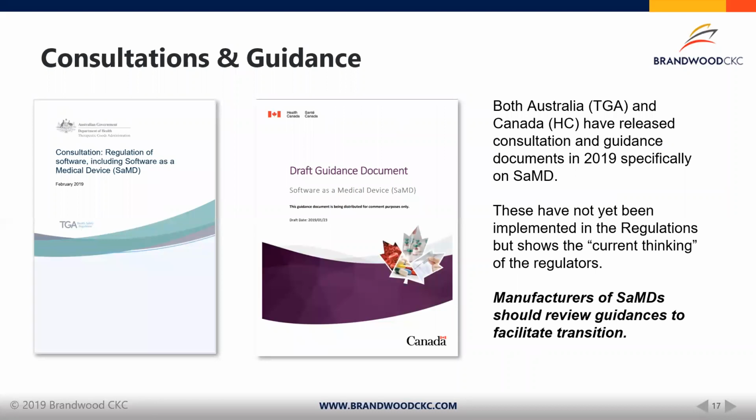In Australia and Canada, there have been some consultations recently. The consultation in Australia, I think, was closed in March this year. Nevertheless, even though those changes have not been formally implemented yet in the regulatory framework, guidance documents provide the view of the regulator as it stands. So both Australia and Canada have released those consultations. They're available online. They're specifically focused on software as medical devices. And as I mentioned before, they represent the current thinking of the regulator. So we highly encourage software developers and manufacturers of potential medical devices to consult those guidance documents as they will facilitate a transition to potential changes in the regulation.